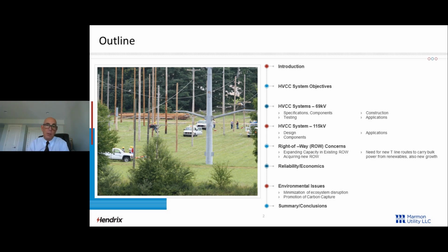For an intro, I'm going to give you a little bit about HVCC, high voltage covered conductor, and what the system objectives are. We'll talk a little bit about the 69 kV spacer cable system and tree wire system, and a little bit about the 115 kV system. Then we'll get right into the main gist of this presentation, our right-of-way concerns. How do we expand capacity in existing right-of-way? How do we get a new right-of-way? Why do we need new rights-of-way? Why do we need new transmission lines? So we'll talk about that a bit.